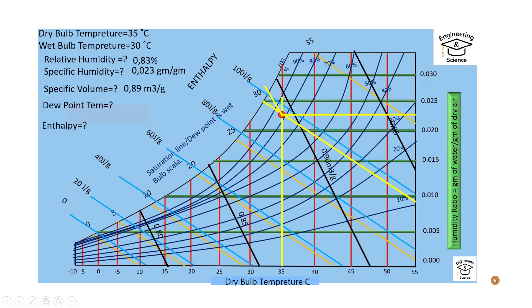Now we have to find dew point temperature. We draw a horizontal line from the intersection point until it intersects the dew point temperature scale. This value is between 25 and 30, so it is about 28 degrees Celsius. That is the dew point temperature.